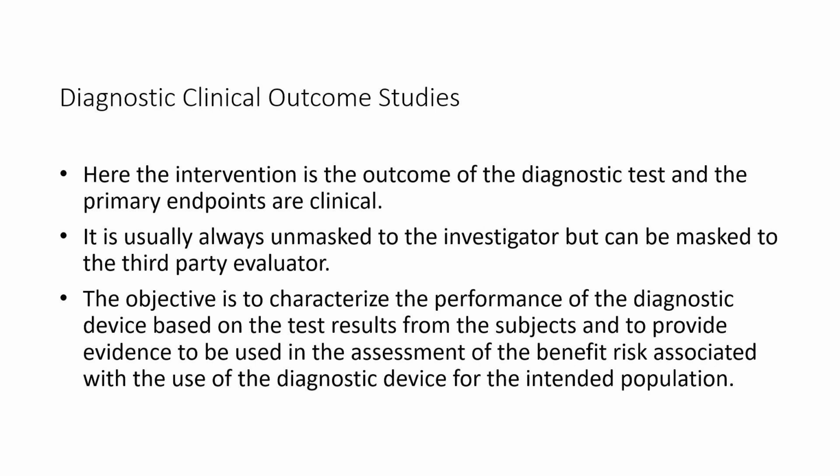So in diagnostic clinical outcome studies, right, where we are trying to diagnose certain things, and we just spoke about biosensors, for example, this is used for diagnosis. Here the intervention is the outcome of the diagnostic test, and the primary endpoints are clinical, right? It is usually always unmasked to the investigator, but can be masked to the third party evaluator, right? If you're doing a clinical outcome study, the objective is to characterize the performance of the diagnostic based device on the test results from the subjects and to provide evidence to be used in the assessment of the benefit risk associated with the use of diagnostic device for the intended population.